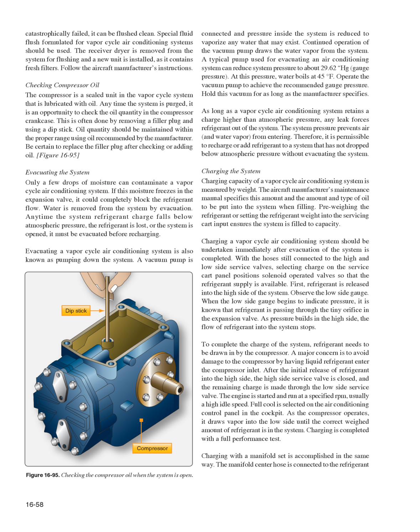A typical pump used for evacuating an air conditioning system can reduce system pressure to about 29.62 inches of mercury, gauge pressure. At this pressure, water boils at 45 degrees Fahrenheit. Operate the vacuum pump to achieve the recommended gauge pressure. Hold this vacuum for as long as the manufacturer specifies. As long as a vapor cycle air conditioning system retains a charge higher than atmospheric pressure, any leak forces refrigerant out of the system. The system pressure prevents air and water vapor from entering. Therefore, it is permissible to recharge or add refrigerant to a system that has not dropped below atmospheric pressure without evacuating the system.